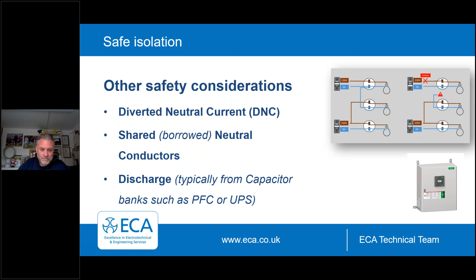And the final one to look out for things are like capacitors. Okay, so you typically find capacitors in power factor correction or UPS. They should be given suitable time to discharge or have a suitable bleeder designed to safely discharge them so you can prove this dead. You'll find them in most electronic circuits. They're in microwave systems, motors, refrigeration circuit, furnaces, smoothing equipment and power factor systems. So bear in mind that there might be a discharge period on these as well.